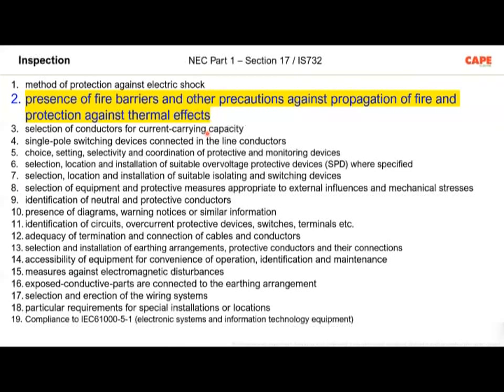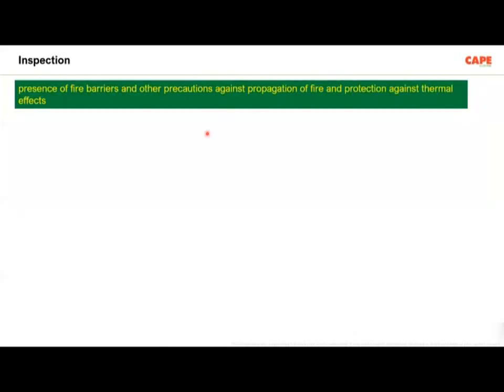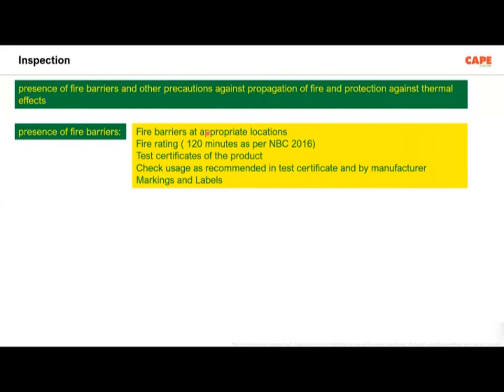Now, as I said, I will explain about the 16 parts. Inspection clause number 2 explains how to inspect the fire barriers, other precautions against propagation of fire, and the protection against thermal effect. In the previous slides, which I skipped, I told there are several conditions required. Condition number 1, presence of fire barriers. In the standard, it is written only as presence of fire barriers.